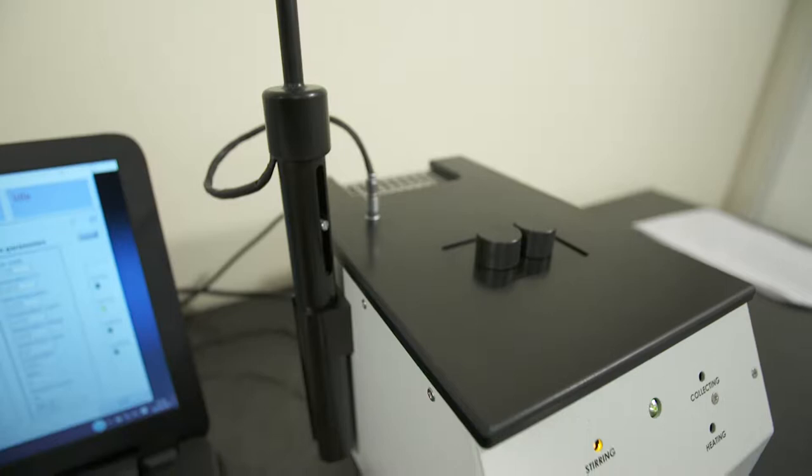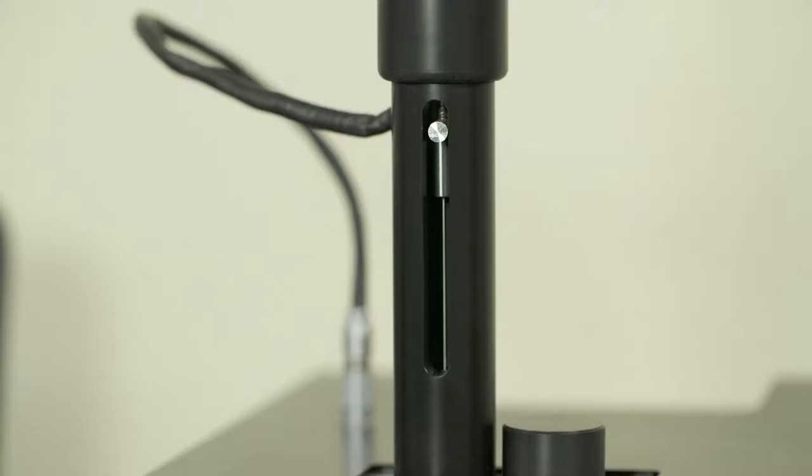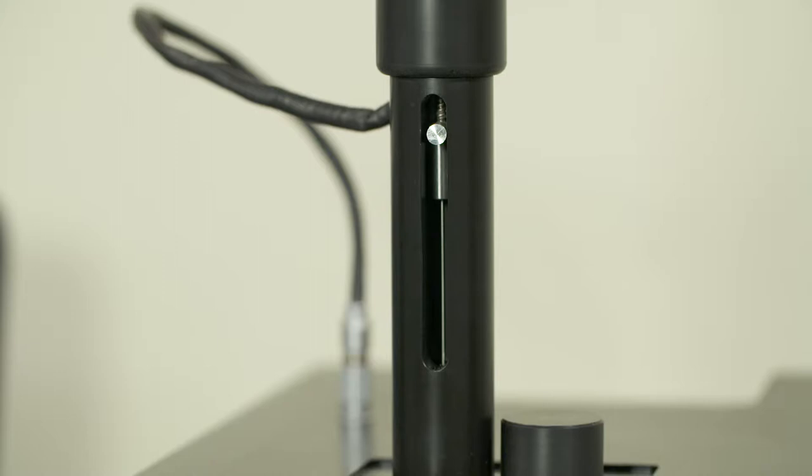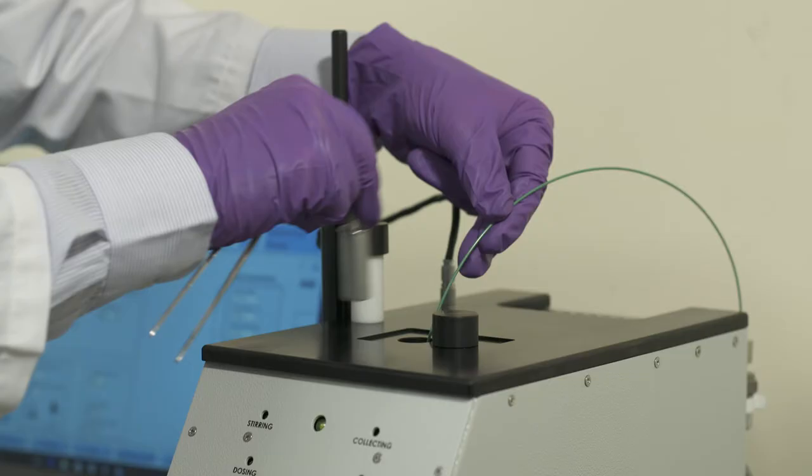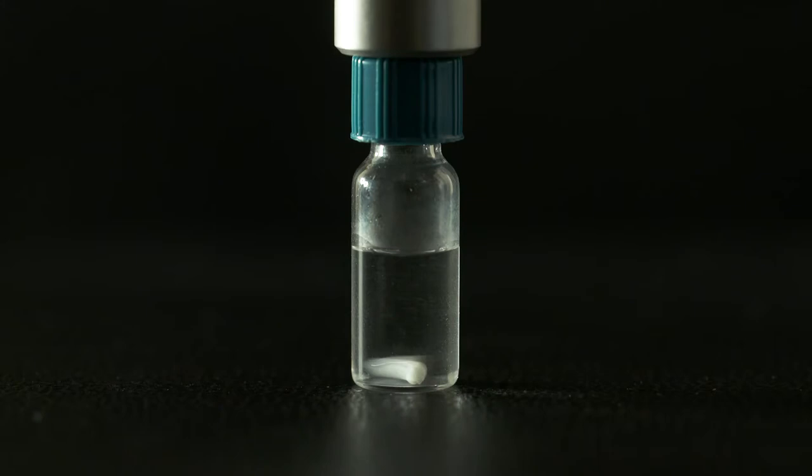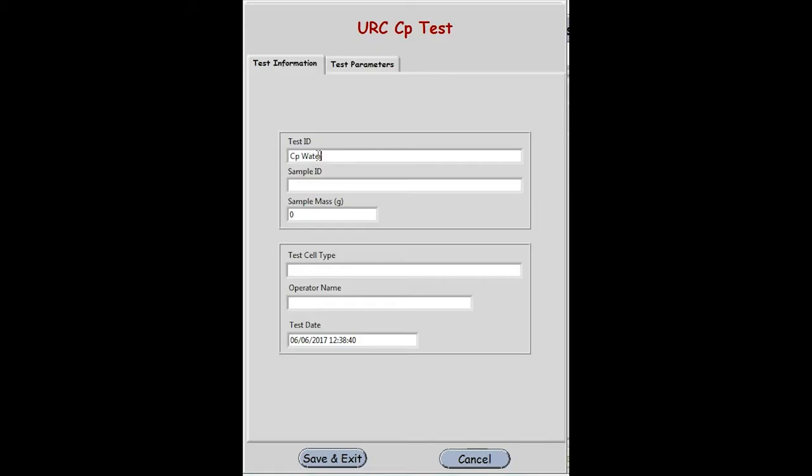The integrated titration tower allows incremental, continuous or single shot titration using 100 or 250 microlitre syringes with magnetically controlled stirring at up to 400 RPM. Manual solid addition is also possible.